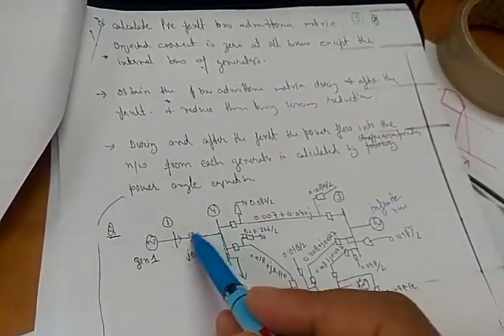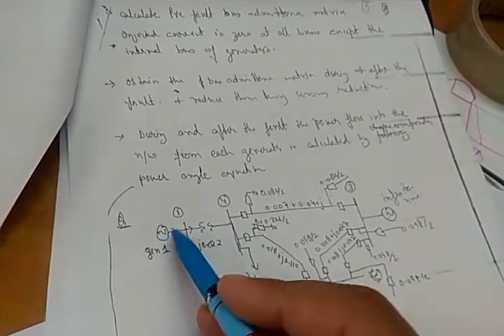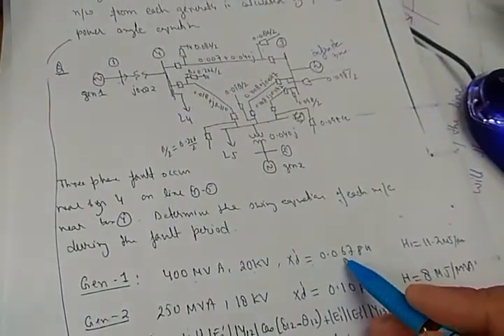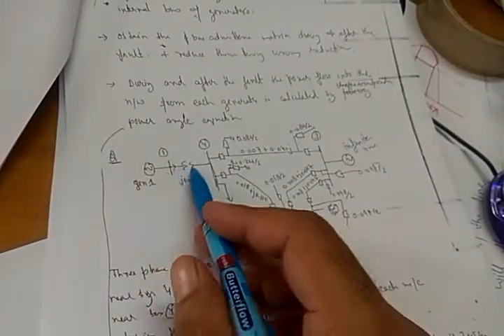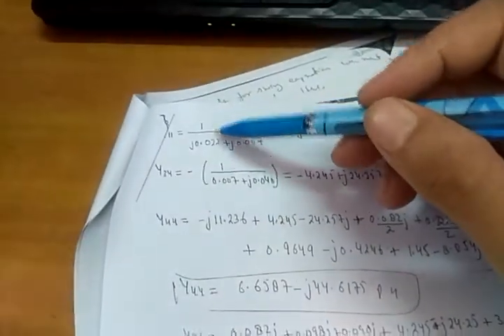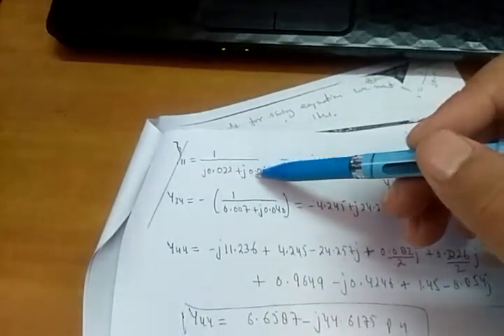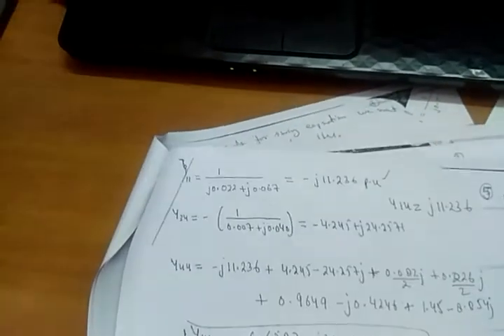So here I have calculated a few elements. Y11, if you will see this Y11. So what is Y11? For Y11, we have one reactance here. This is the reactance of the transformer, plus I have a generator which has some reactance, which is given by the transient reactance as 0.067. So bus 1 is connected to two reactances. So here I am calculating. I have to calculate the admittance, so I will take the reciprocal of the reactances. So 1 divided by j0.022 plus j0.067. So I will calculate Y11 here.